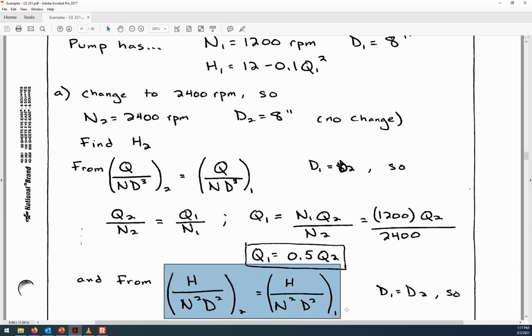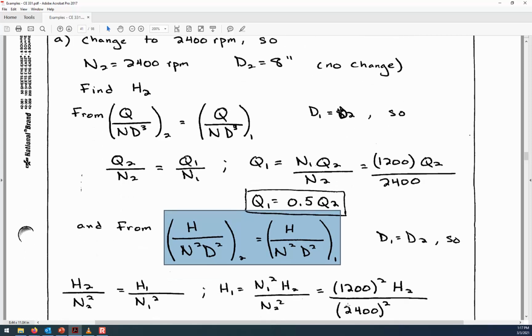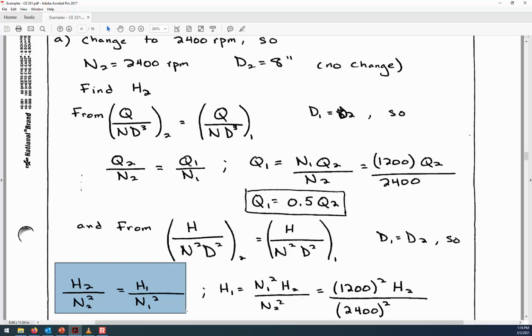The diameters again are the same, so we can cancel that term out. So our simplified scaling law, once we omit any relationship of the diameters, is that the head of the second pump divided by the rotational rate of the second pump squared is equal to the head of the first pump divided by the rotational rate of the first pump squared. All right, so rearrange that to solve for H1, because that's the substitution.